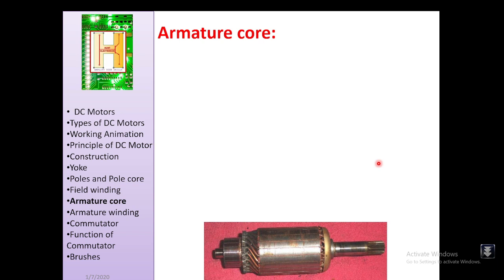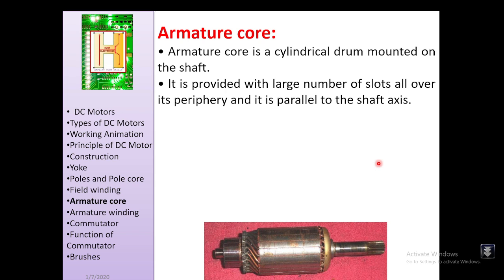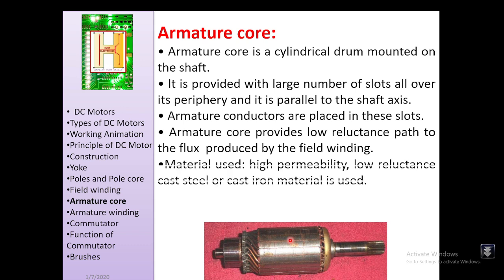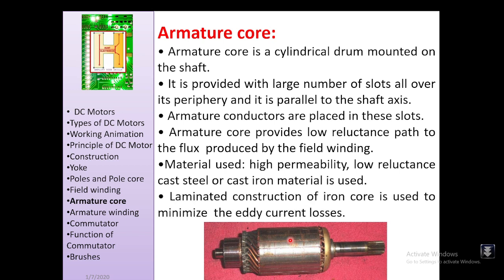The armature core is a cylindrical drum mounted on the shaft with a large number of slots around its periphery, parallel to the shaft. Armature conductors are placed in these slots. The armature core provides a low-reluctance path to the flux produced by the field winding. It is made of high-permeability, low-reluctance cast steel or cast iron, with laminated construction to minimize eddy current losses.